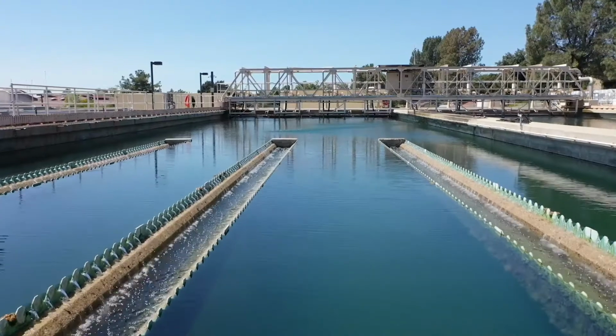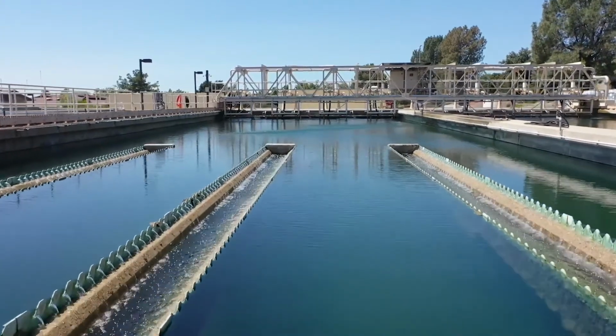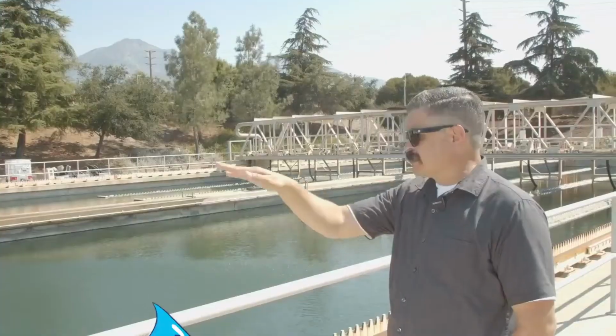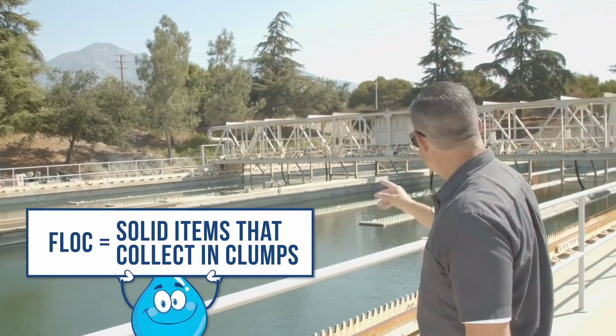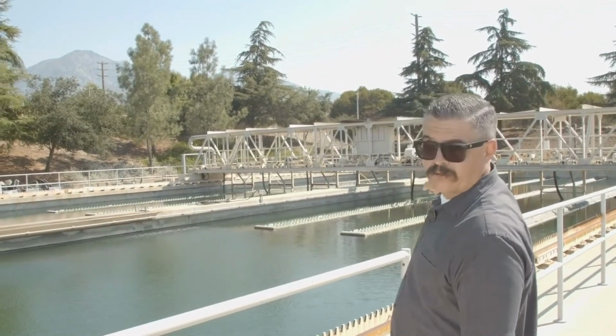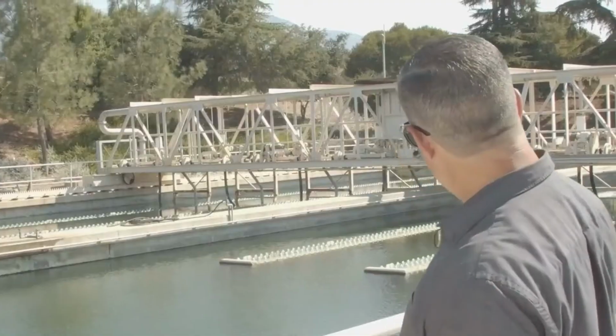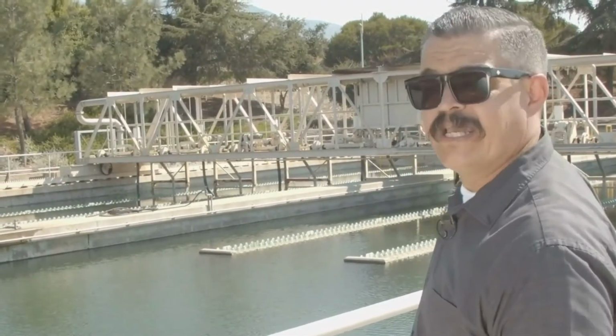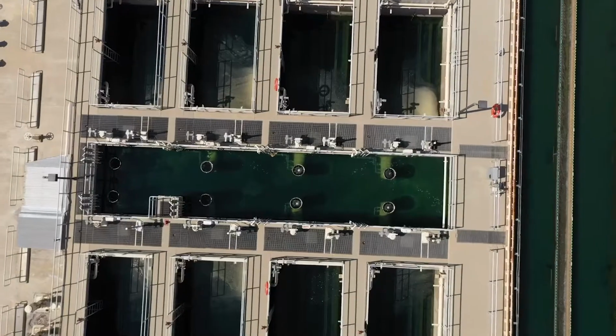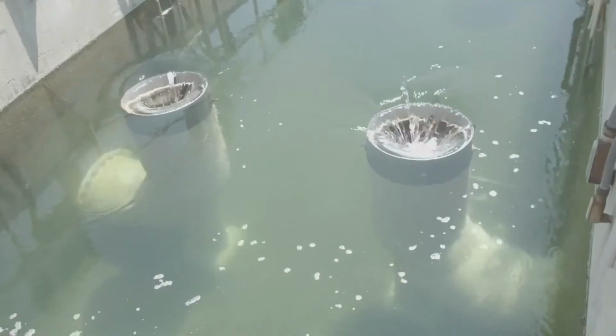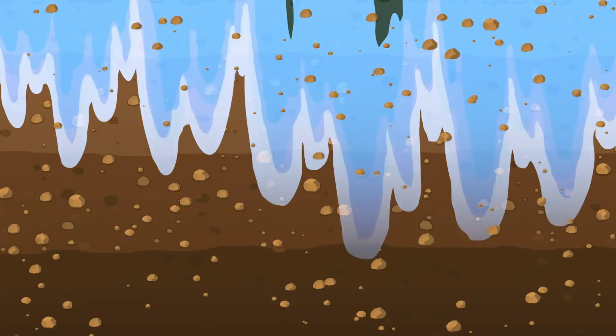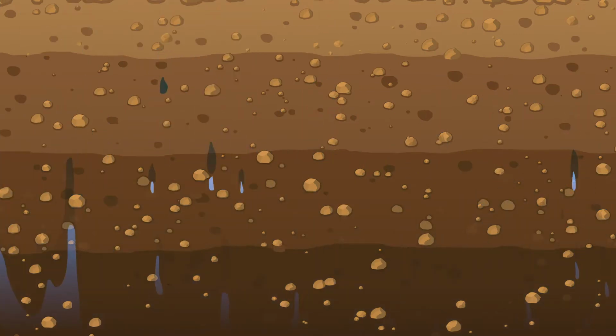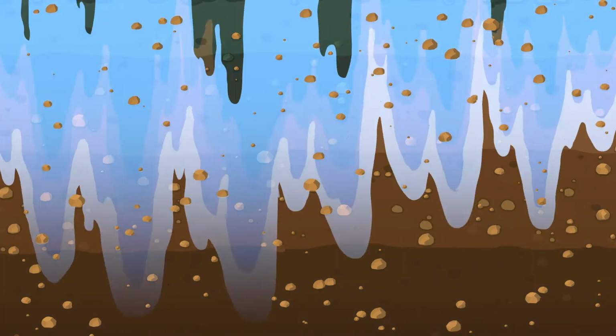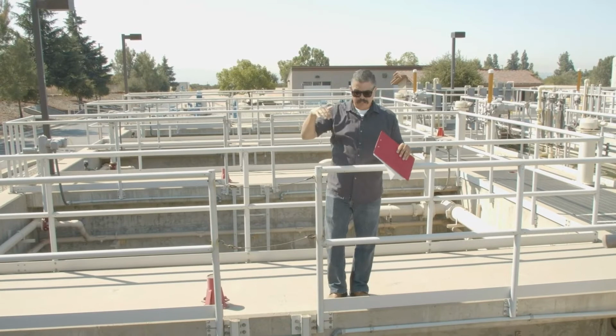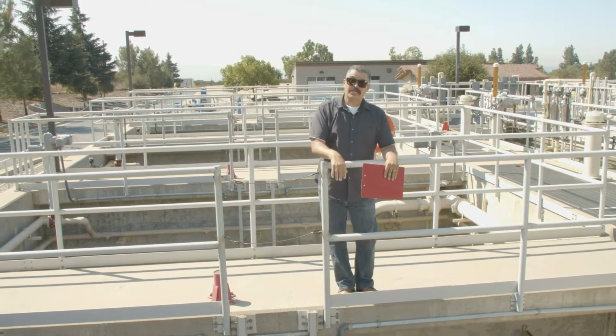And now we've moved on to the 3rd stage, which is the sedimentation process. The goal for that is to allow the floc to settle out prior to the water reaching those catch troughs. The clean water is being caught into that trough and then redirected over to our filters, which is the next process. Once it's here, it starts to percolate through the filter in the same way that water, when it rains or during a storm, percolates through the strata of the earth. It's doing the same thing here in this filter.